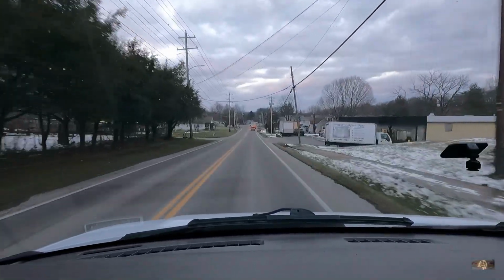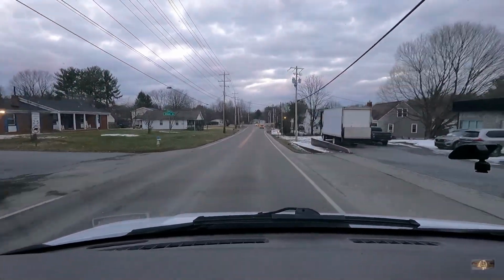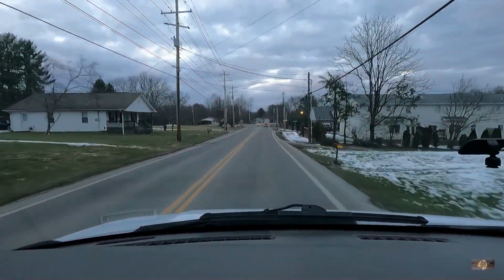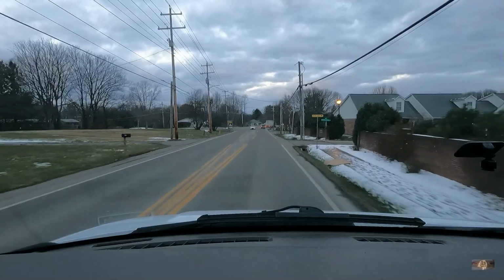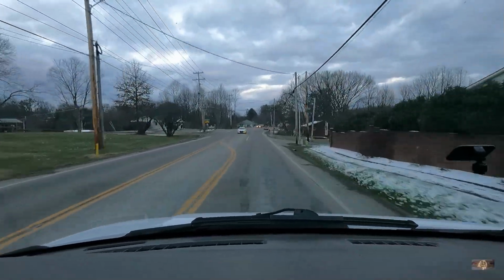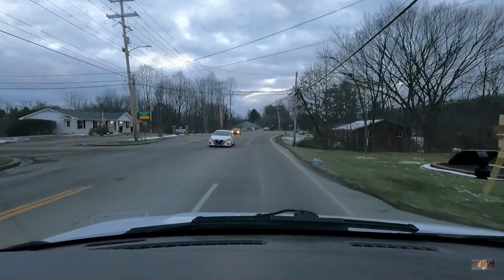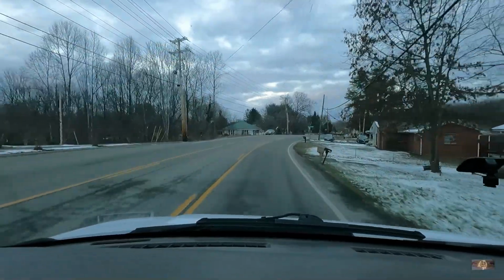It just has inadequate ductwork, with a massive temperature split from the heat strip running along with the heat pump. He just needs new ductwork. I told him we could try enlarging the return to see if that helps, and we'll do a static pressure test.